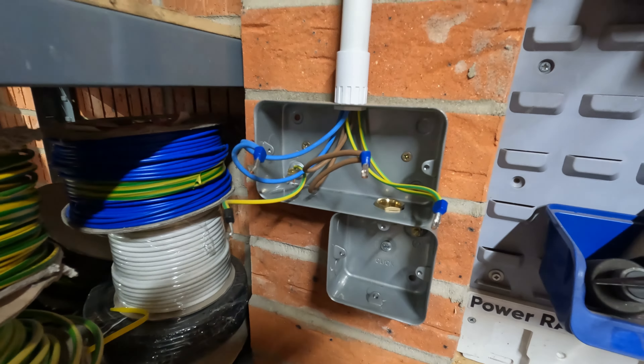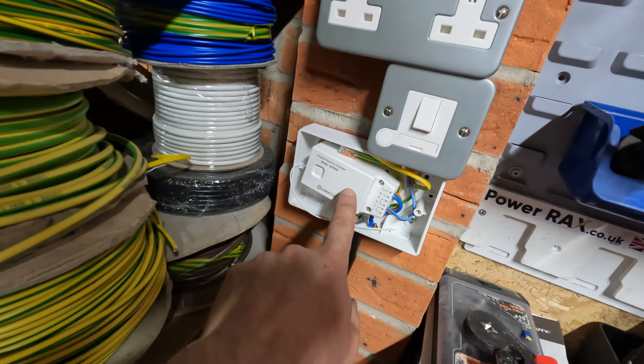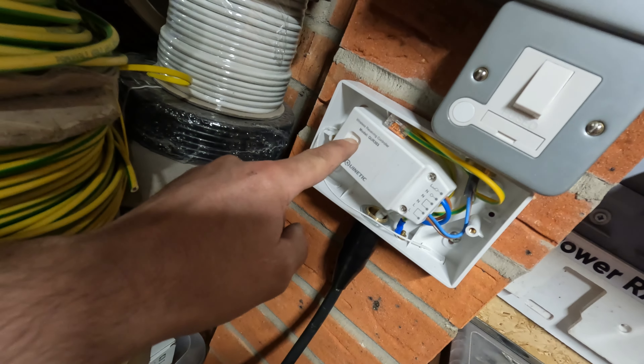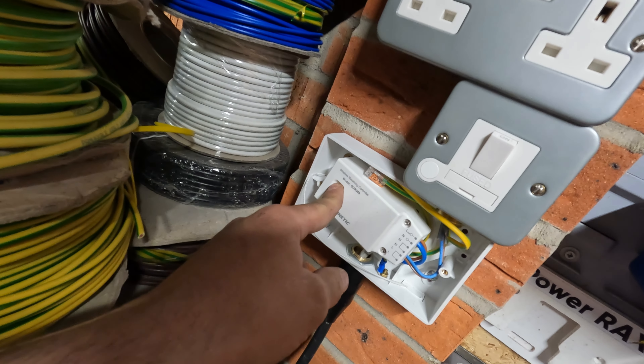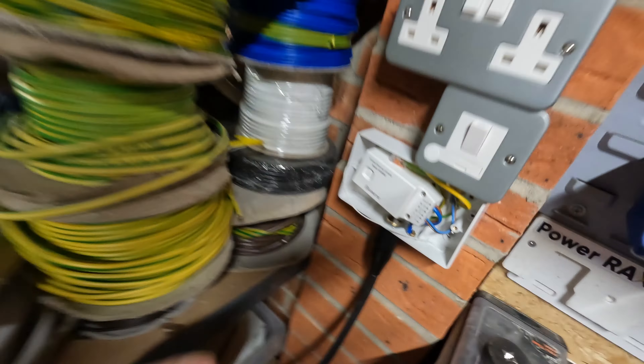We've got the socket, spurred off into the fused connection unit, which has come down to the Quinetic wireless receiver. The armoured cable is banjoed in and the armour is earthed. Now I just need to pair the Quinetic switches — turn the receiver on into pairing mode, click the first switch, then the second. Both are now paired. Let's go outside and see if it's all working.